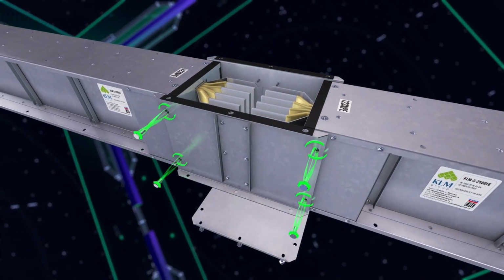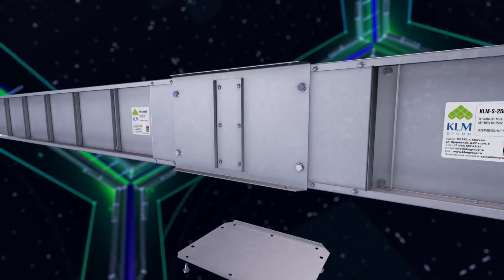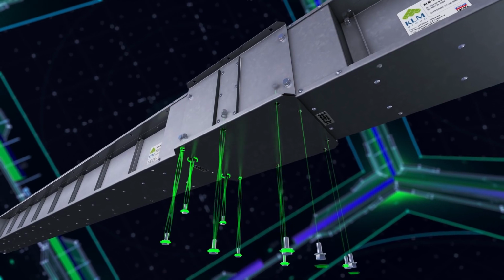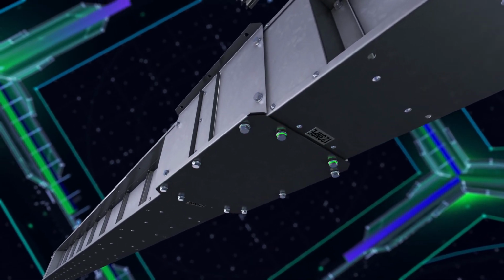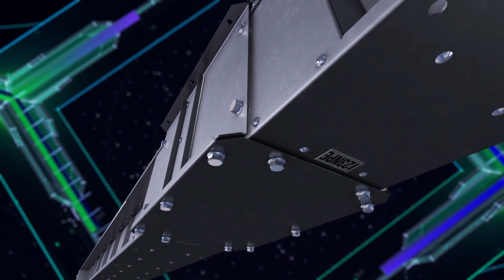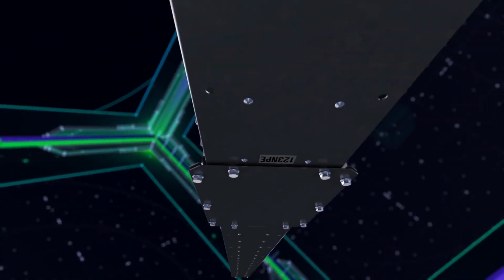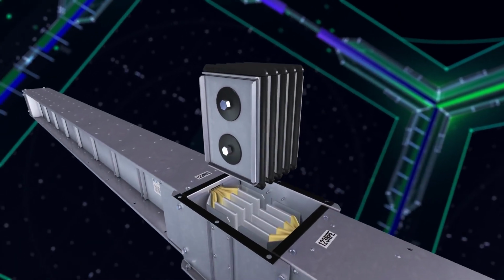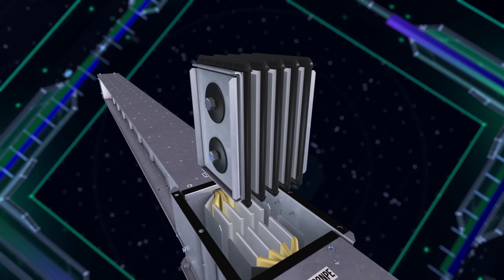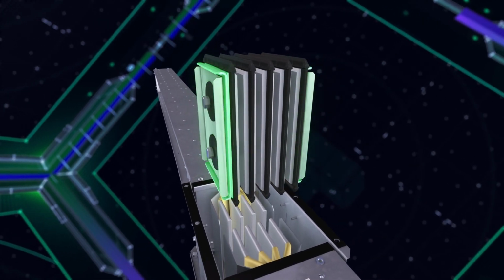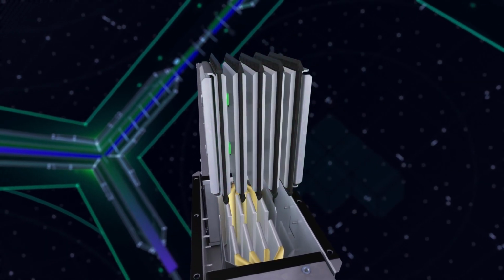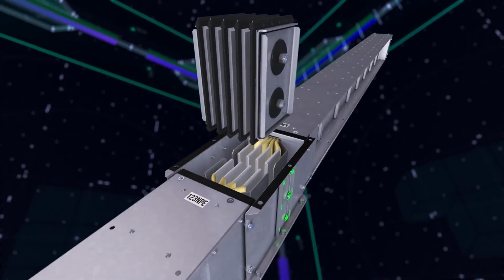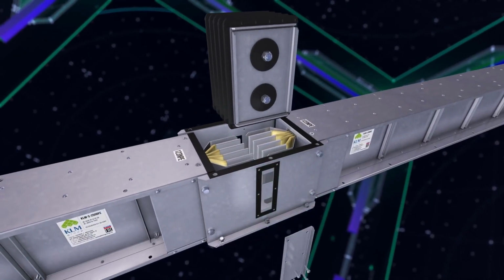Attach the two side covers and one bottom cover of the junction unit using the bolted connections. In this step, the bolts must be hand tightened so that there is a gap between the side covers and the housing. Check the components of the junction unit to ensure there is no damage and that the junction unit insulators are intact. There must be no cracks or chips. Remove the plugs from the side covers of the junction unit.